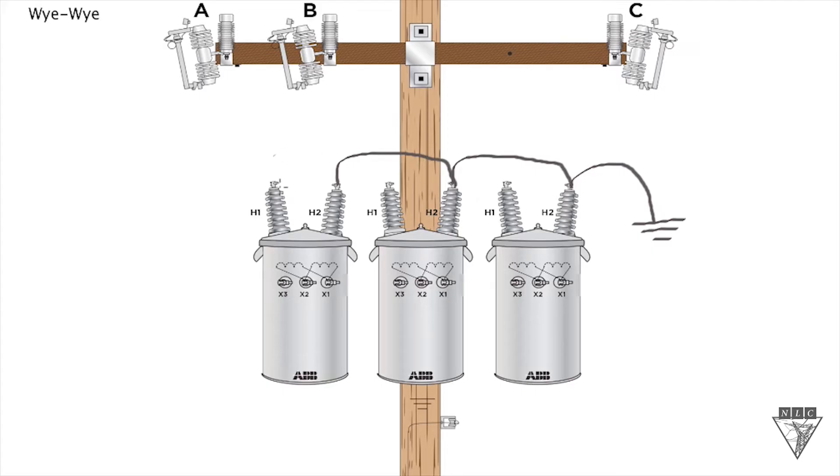Now the second part of this is you just simply run each H1 bushing and run a wire up to each phase. So we'll go to A phase there, center one will take to B phase, and this far right one will take over to C phase. And this is the connection on the primary side of a YY.